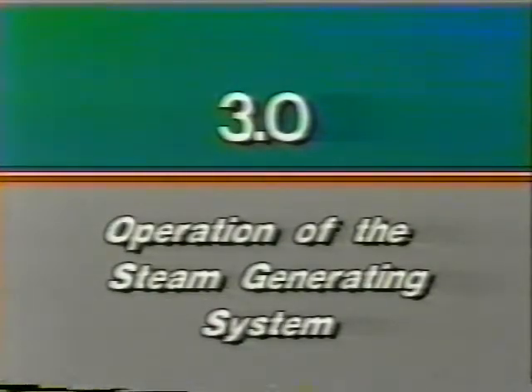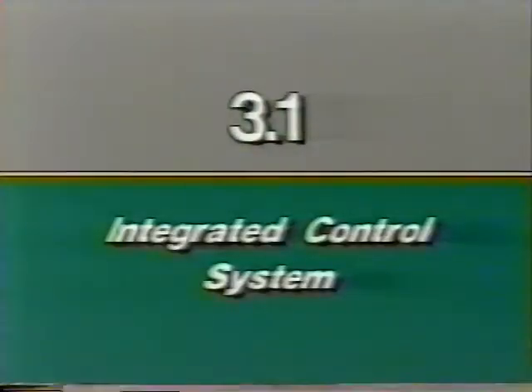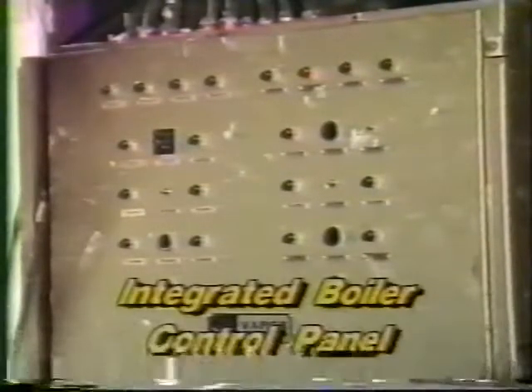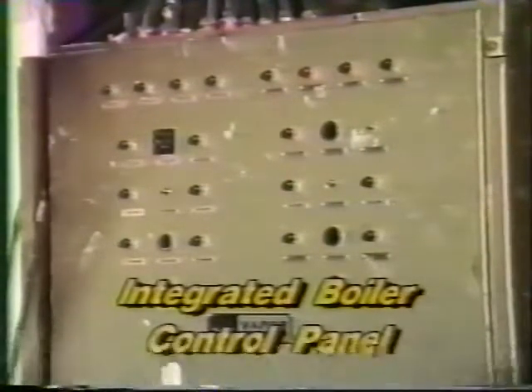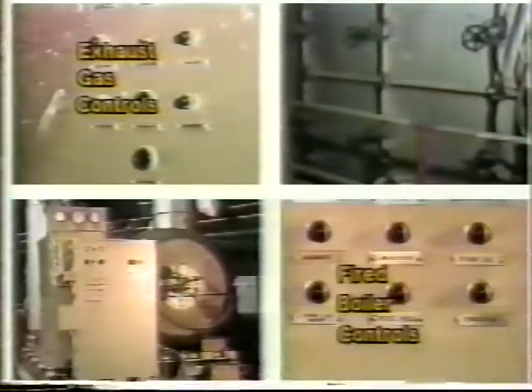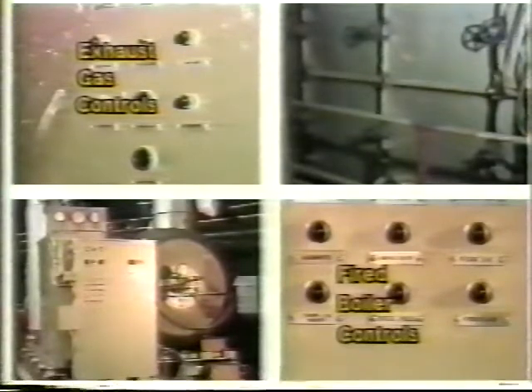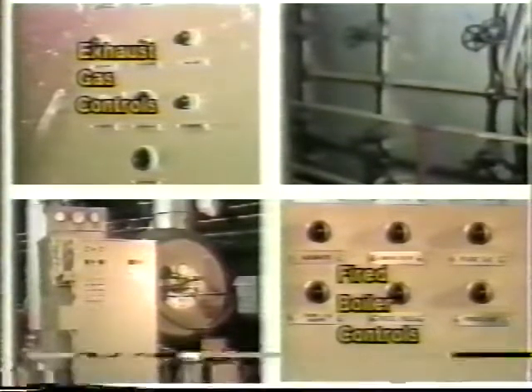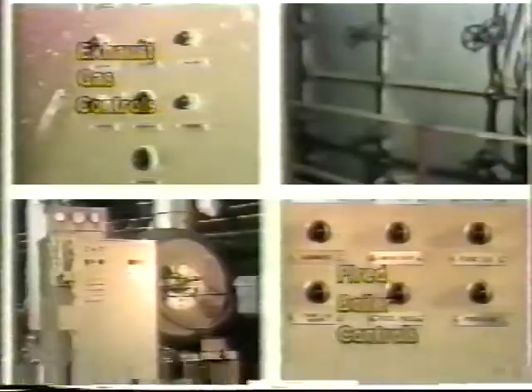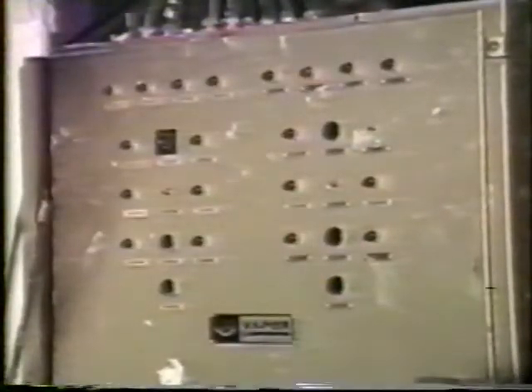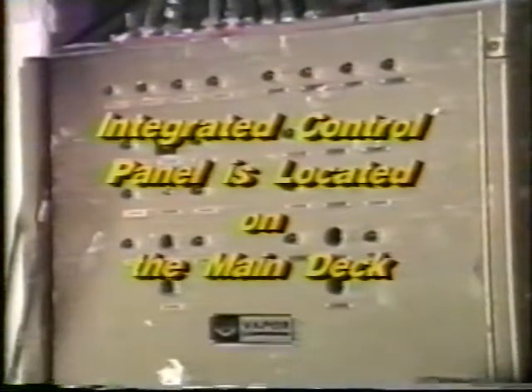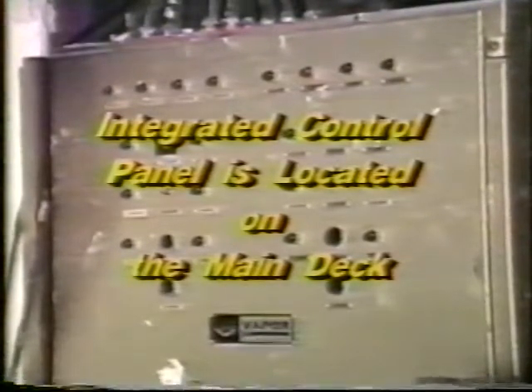Operation of the steam generating system. Integrated control system. The integrated control system is designed to supply and control the required amount of feed water to the exhaust gas boiler and the Circulatic boiler. Other controls for the exhaust gas boiler are also located at the integrated control system, but the fired boilers have separate controls for setting operational parameters and valve positions for generating steam. The integrated control system, which contains the controls for the common feed water pumps to both boilers, is located on the main deck.